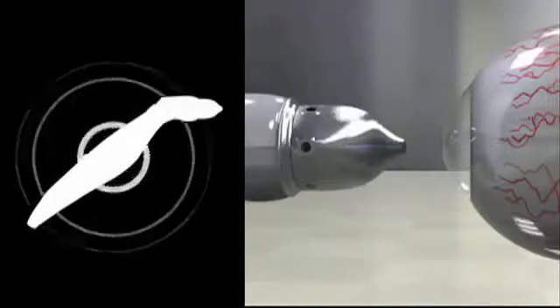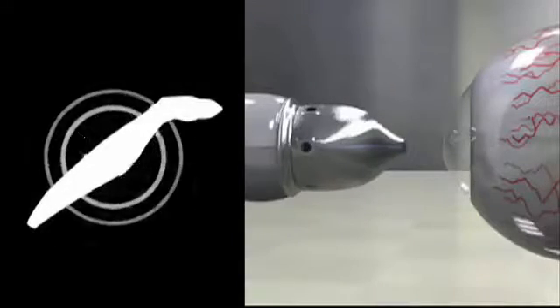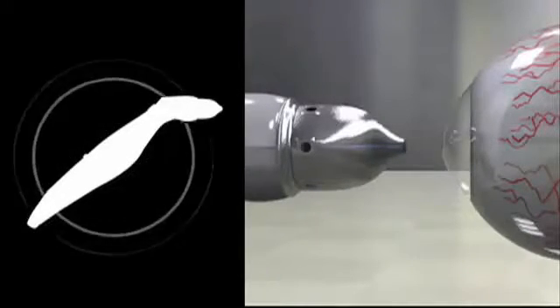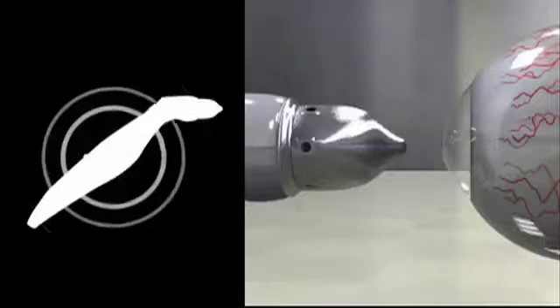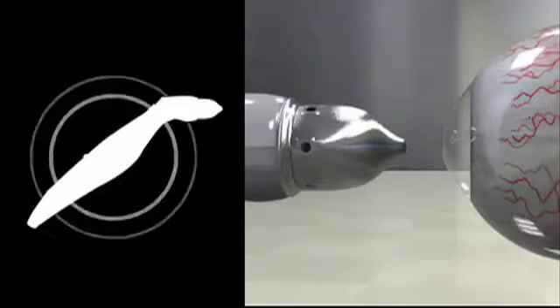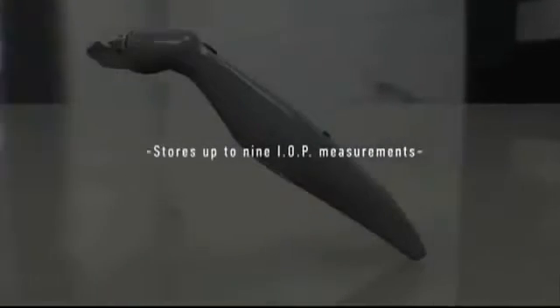As you gently tap the cornea, you will hear short chirps followed by one longer chirp. The longer chirp indicates you have obtained an IOP measurement. The number of short chirps can vary. The AccuPen Vet has a proprietary algorithm which eliminates the need for a confidence factor. The AccuPen Vet has the ability to store 9 IOP measurements.